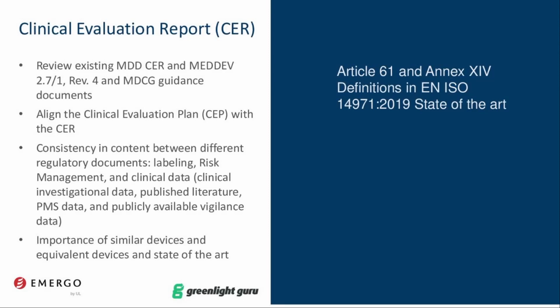And then again, two other additional concepts that are going to be important. Similar devices, which was defined in the MDCG document, are required within the Annex 2 MDR technical documentation file, as well as within the clinical evaluation report. So that's the importance of similar devices, and equivalent devices if you use that regulatory strategy. But we really feel that in the context of the MDR, unless it's a device within your own device portfolio, the concept of equivalent device is really not one that can be used because of the increased burdens described in Article 61, Section 5, as well as in Annex 14, Part A.